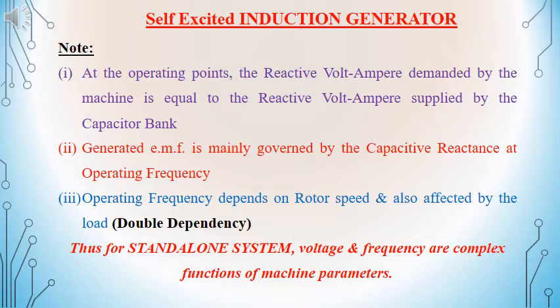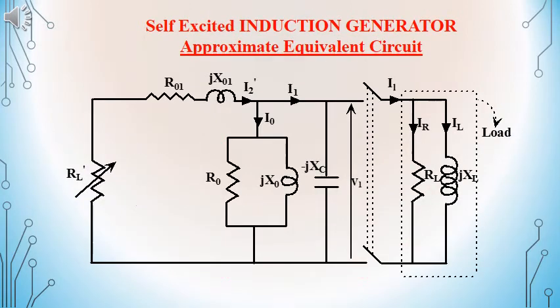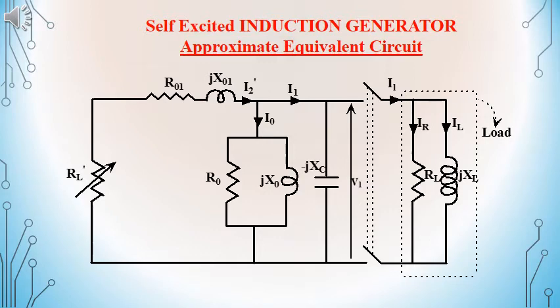The generated EMF will be governed by the capacitive reactance at the operating frequency. Here we have the approximate equivalent circuit given for a self-excited induction generator. On the left side, we have a variable resistance RL dash that is shown, which is equivalent to the prime mover providing the active power to the induction generator. The active power will be supplied to R01 and R0 as losses in the system, and the remaining will be supplied to the load given as RL. The entire reactive power, that is the lagging reactive power, is supplied by the capacitor connected, given by the capacitive reactance XC.